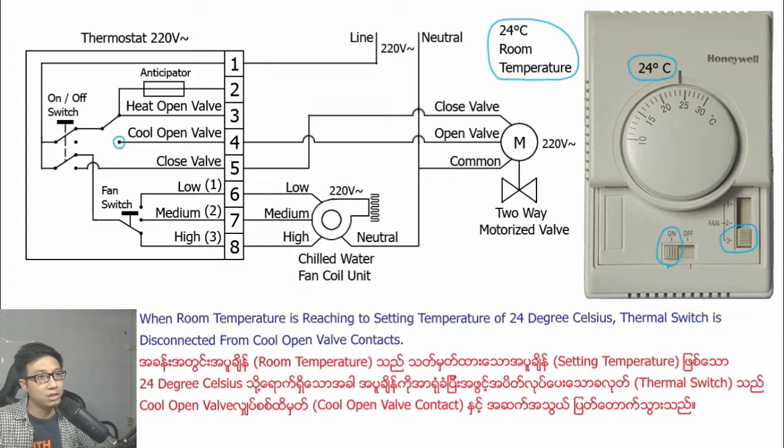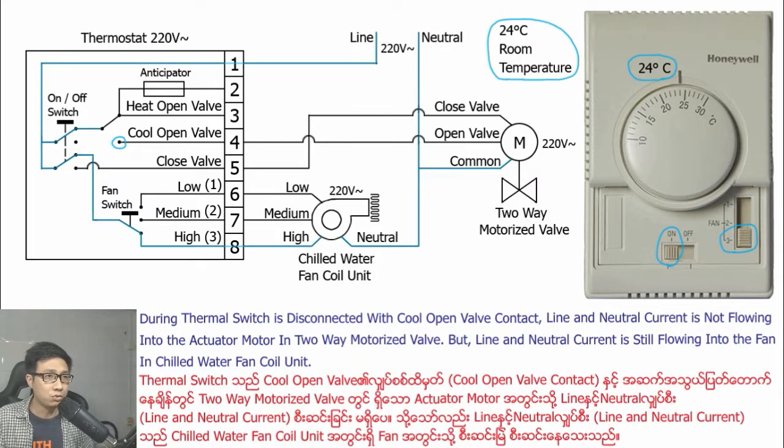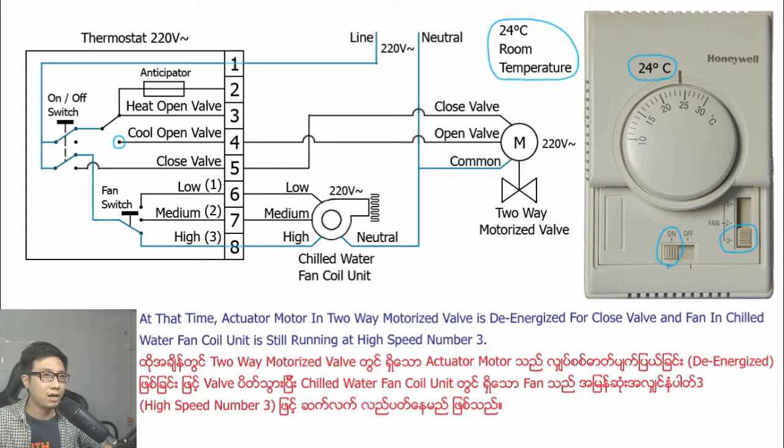When the room temperature reaches the set temperature of 24 degrees Celsius, the thermal switch disconnects from the cool open valve contact. Line and neutral current stops flowing into the actuator motor in the two-way motorized valve, but current is still flowing into the fan of the chilled water fan coil unit. At that time, the actuator motor is de-energized and the valve closes, while the fan continues running at high speed number three.